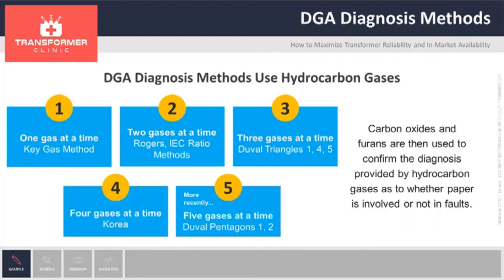There are several DGA diagnosis methods available using either one, two, three, four, or five hydrocarbon gases at a time, for instance in the triangle and pentagon methods. Carbon oxides and furans are then used to confirm the diagnosis provided by hydrocarbon gases, as to whether paper is involved in faults or not.